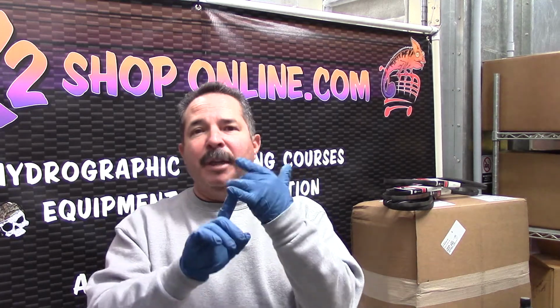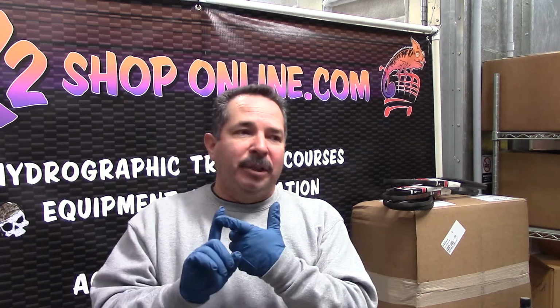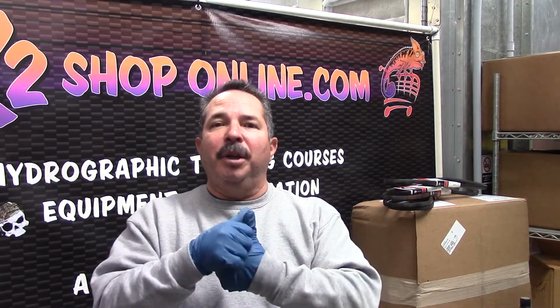The other things that come to mind, drain your tanks on a regular basis. That's more of a monthly thing, but if you haven't done it in a while, now's a good time. So again, your intake filters, belts for your motors, your fan motors, exhaust fans on the roof, especially when they're on the roof and you can't get to them. It's going to take you a while. Just plan on doing it. Get it done. Get it over with. Oiling and greasing your motors, oil changes on your compressors, drain your lines, drain your tanks.